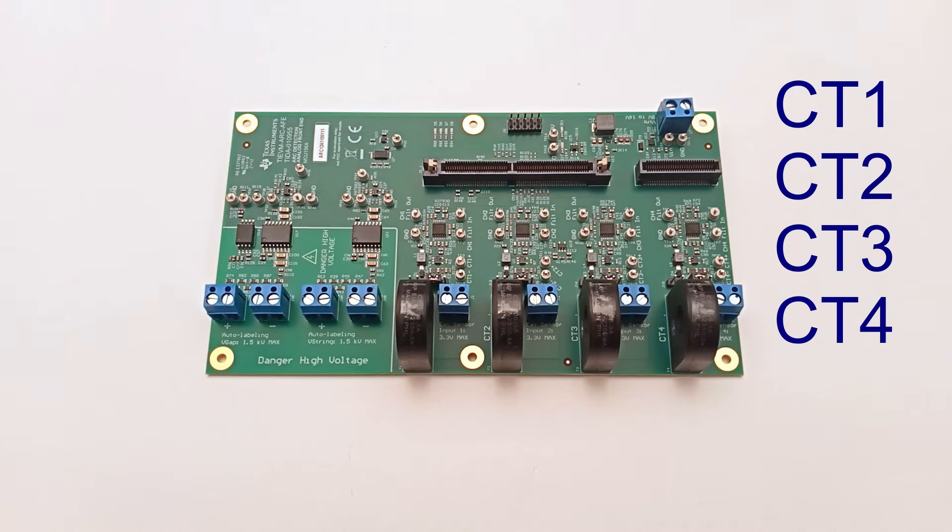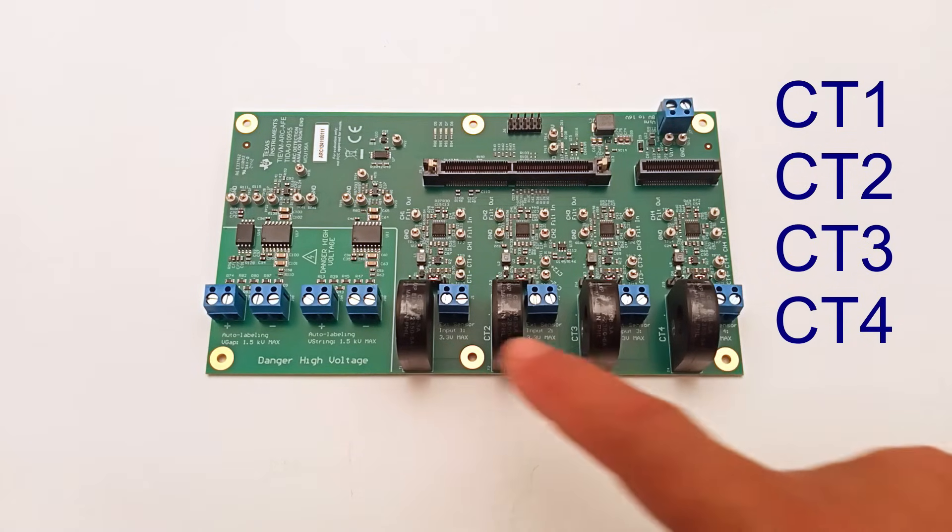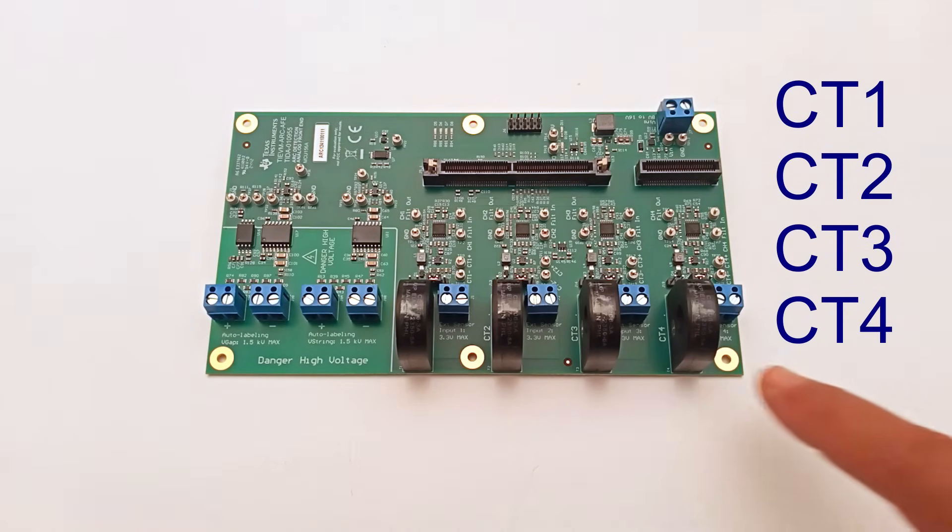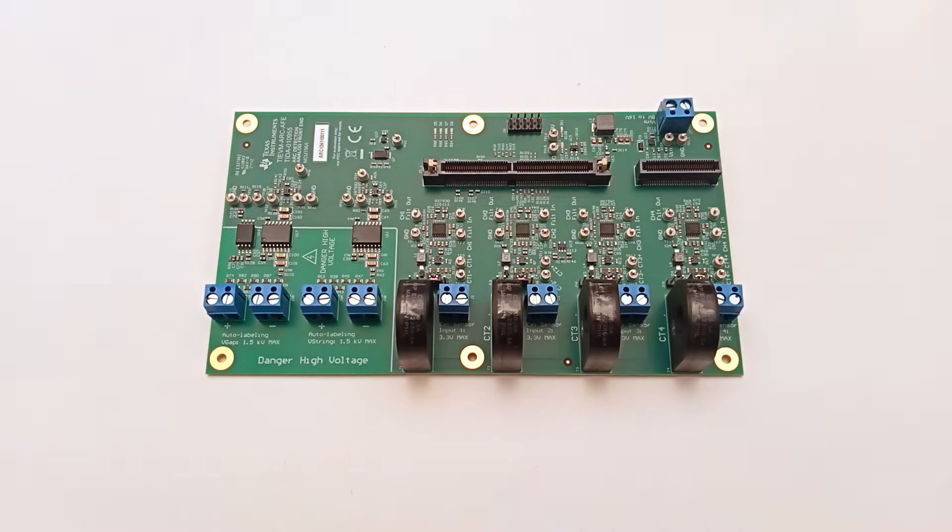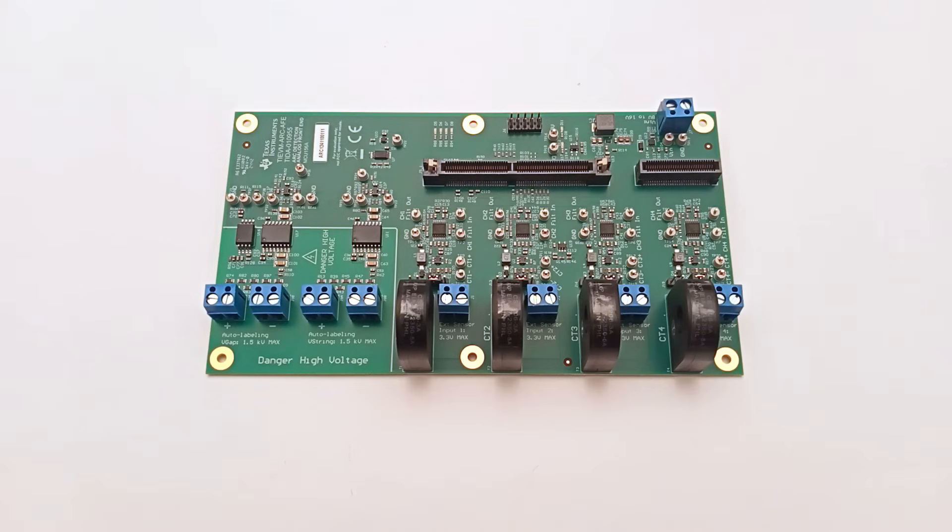CT1, CT2, CT3, and CT4 are the four onboard current transformers, one for each arc detection channel. They extract the AC component of the string current and send it to the gain and filter stage and then to the ADC.